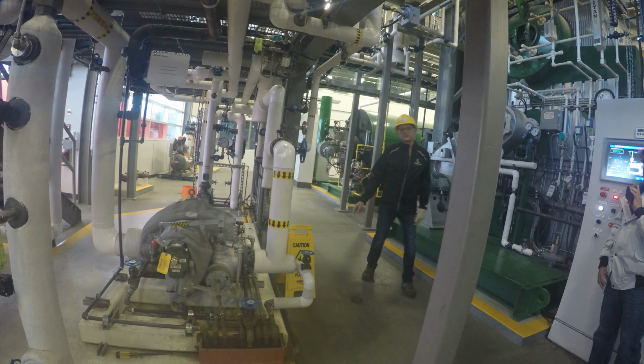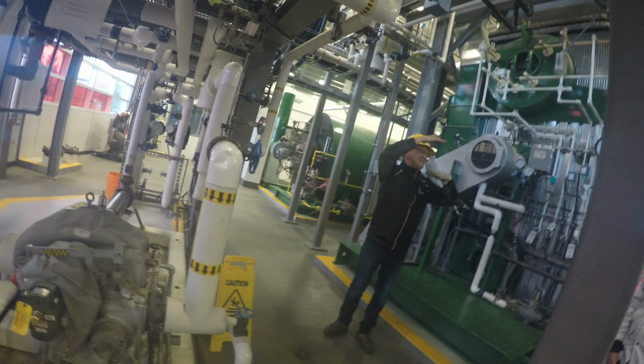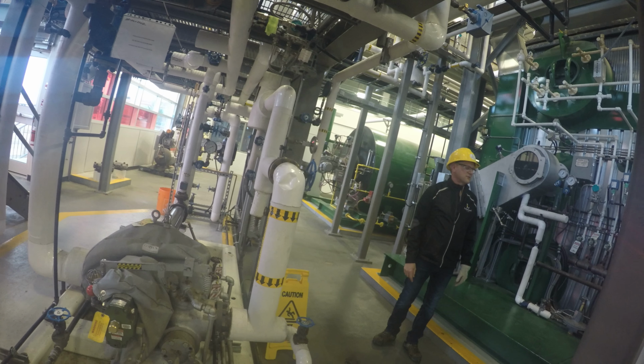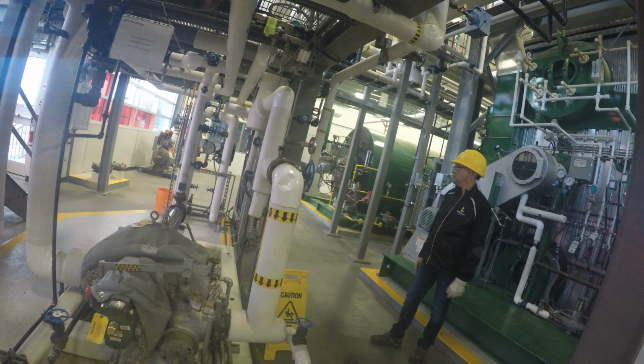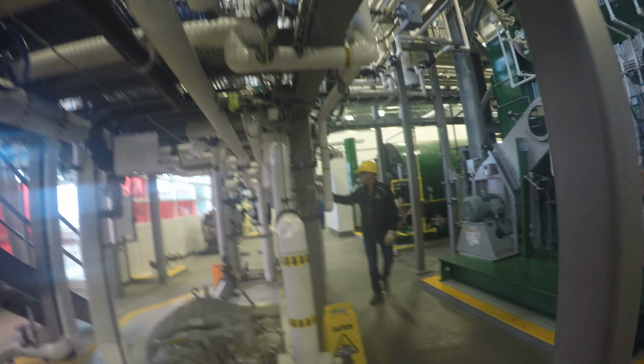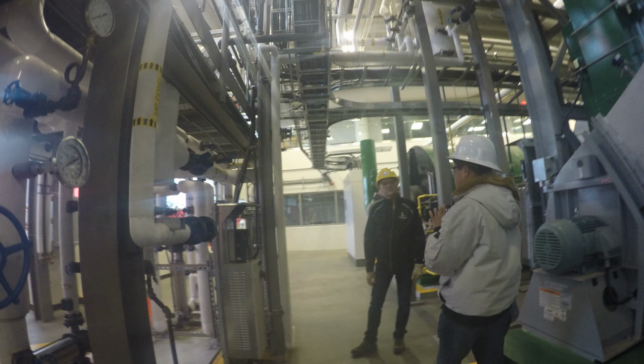We can run those things up to about 2400 kPa, because if your boiler is operating at 1400 kPa, you need your pump to push at about 1800 kPa so you can get water in above the pressure of the boiler, right? So the only way you're going to move water in there is you've got to have a pump that will put out. So they're all VFD driven. So these are your VFDs that drive your motors. So we can ramp those things up and down however we want, right?